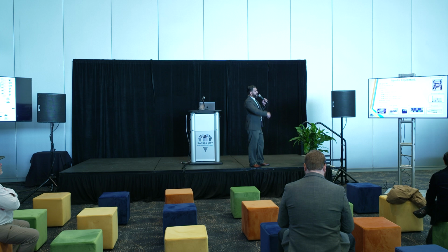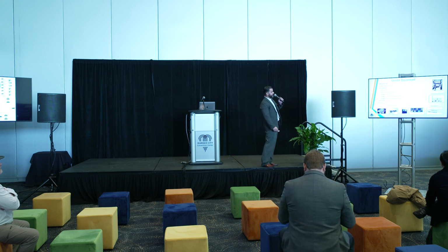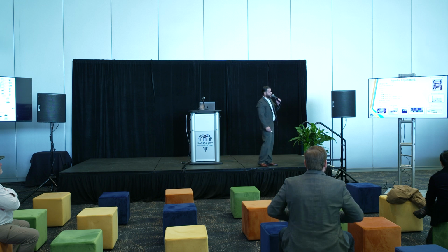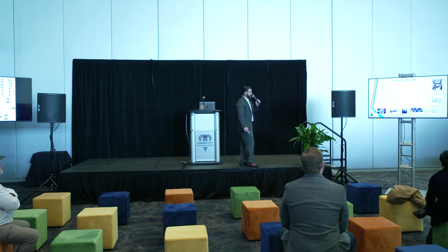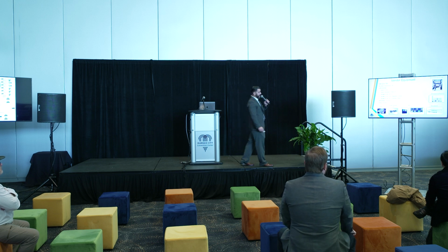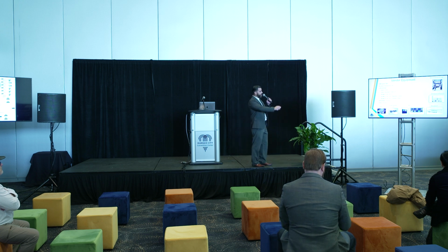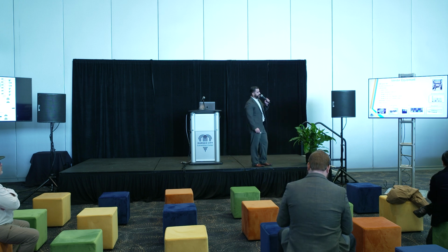As far as the LAN devices go, behind Hub 1 and 2, these were your polling devices that were polling out to the remote spokes, the devices sitting on the LAN side. Hub 1 had a SEL RTAC sitting behind it. Hub 2 had a Novatech Orion LX. We had 6 spokes, but there were SEL devices sitting behind 1, 3, and 5 only for testing purposes. There was an SEL 651R behind Spoke 1. Site 3 had a 2431 regulator control box. Spoke 5 had a 351S breaker relay box.